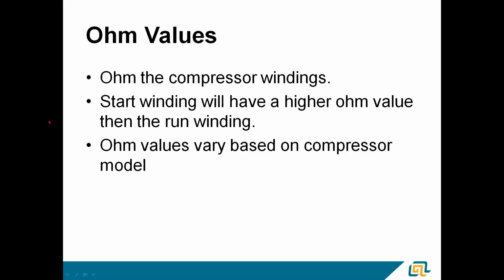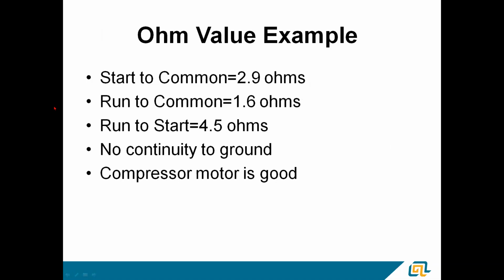The ohm values vary based on compressor model. If you ever got to know for sure, I can get you exact ohm values for each compressor model, so that you can make a confident diagnosis. But the general rule of thumb, and these are just numbers that I pulled out of the hat, the math was easy: ohm your start to common, your start winding, you get about 2.9 ohms, let's say. Then you ohm your run to common, you get 1.6 ohms. So right there, you've got the first rule: start winding slightly higher than your run winding.